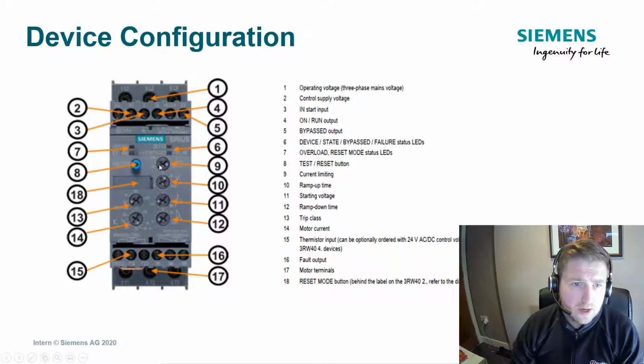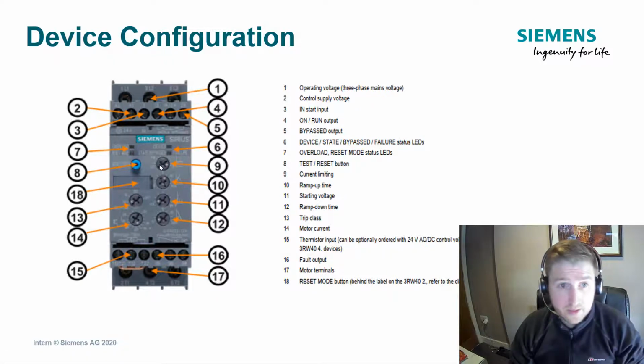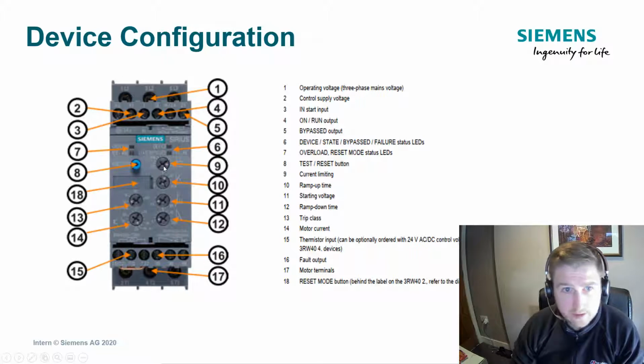This next pot at the top right is the current limitation function, which can have a bearing on how the soft starter starts. A soft starter typically functions through voltage regulation, but if this current limitation were set to, say, 2 times the rated current, and during startup you would typically achieve 4 times the rated current, the soft starter would regulate the current to 2 times the rated current until it reaches full speed. But if you don't reach full line voltage within the time frame you've set on the pot below it for the ramp up time, it won't have reached bypass mode, it won't switch out, and it'll go into fault.